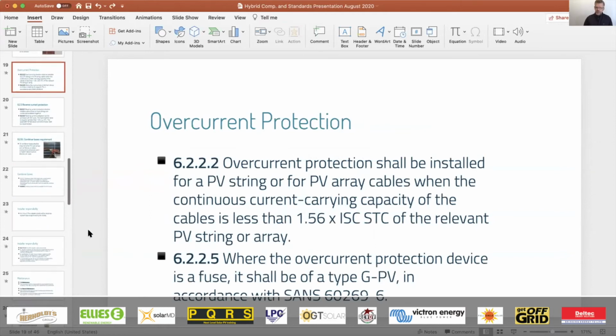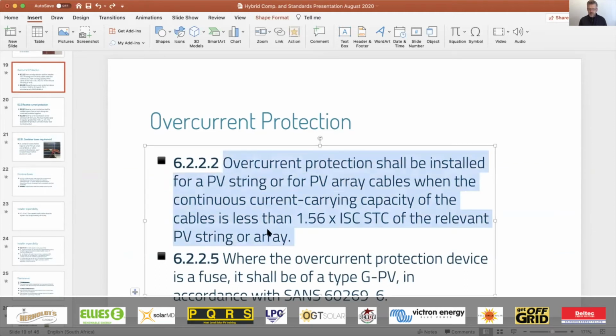Overcurrent protection. Overcurrent protection shall be installed for a PV string or for PV array cables when the continuous current carrying capacity of the cable is less than 1.56 times the short circuit current. That's what we saw in one of the previous slides as well. This, of course, is in a completely different section of the standard. Then it says where the overcurrent protection device is a fuse, it shall be of a type GPV.